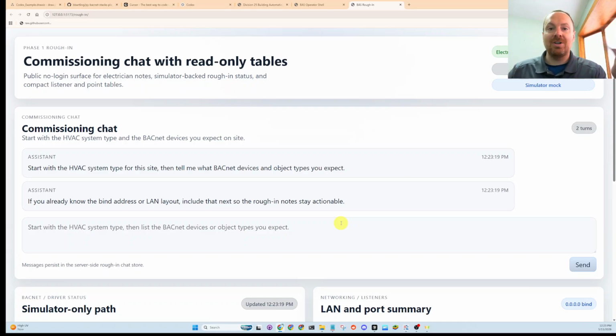Let's say the power is turned on to the devices, and then you need to know if BACnet devices are coming online or offline, if sensors are reading values, in the early stages of functional checkout. So I'm trying to tailor this application to start with the electrician and typically the building automation controls technician doing point-to-point commissioning. Basically we need to know: are all devices online, are they communicating, what are the points, are all the sensors reading values, let's test the sensors, valves, and dampers. So this is a very early stage of building the building automation system.